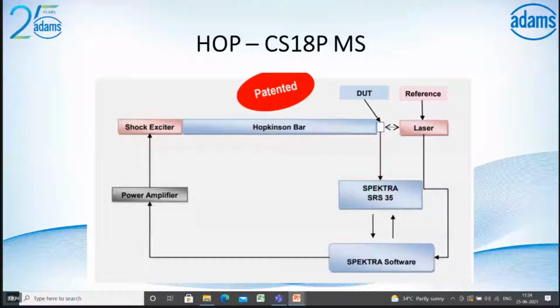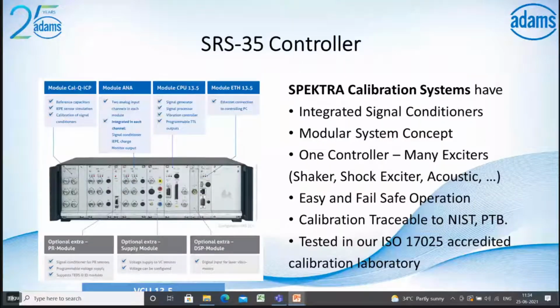And the SRS35. It's a vibration control unit which has an integrated signal conditioner, and it's a modular system concept. With the one controller, we can use it for different applications such as acoustics, shock and vibration. It has a module called CAL QICP, for the electrical calibration of signal conditioners, and it has the analog input module, where you can connect your microphones and accelerometers. It has inbuilt signal conditioners, and it has two outputs for monitoring the signals from the sensors. And it has an inbuilt CPU, which gives the output voltage to the exciters for the different applications such as acoustics, vibration and shock.